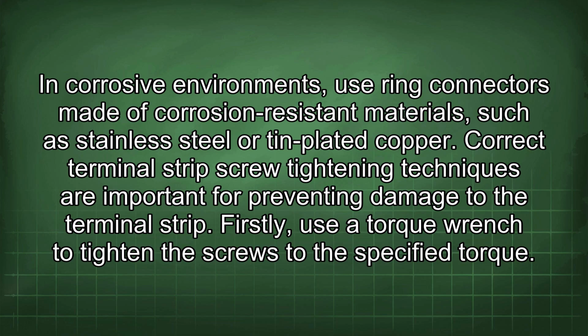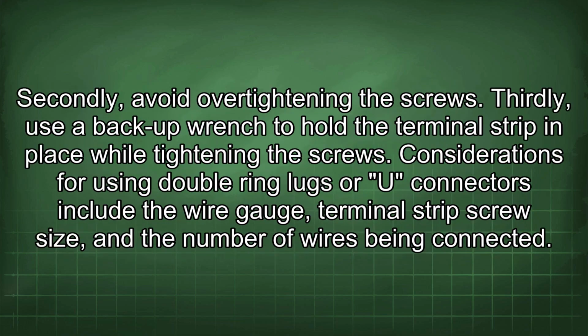Correct terminal strip screw tightening techniques are important for preventing damage to the terminal strip. Firstly, use a torque wrench to tighten the screws to the specified torque. Secondly, avoid over-tightening the screws. Thirdly, use a backup wrench to hold the terminal strip in place while tightening the screws.